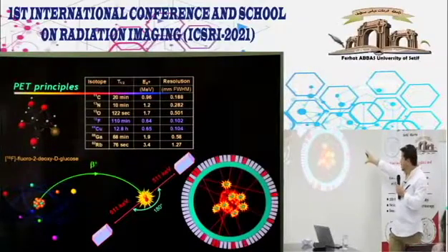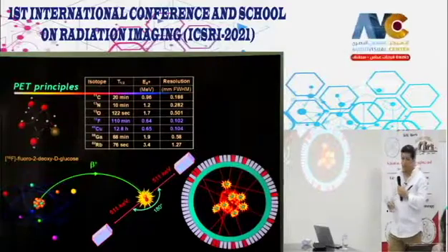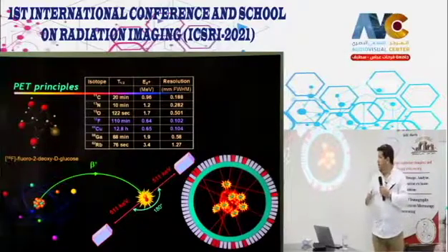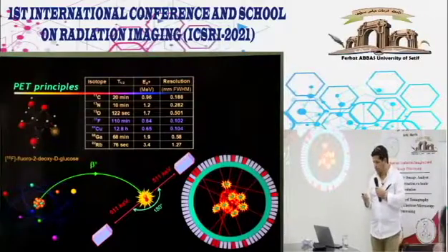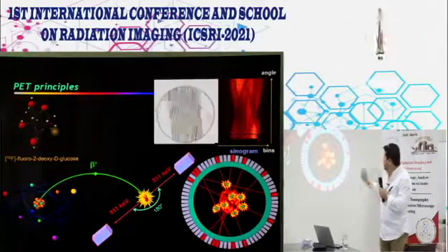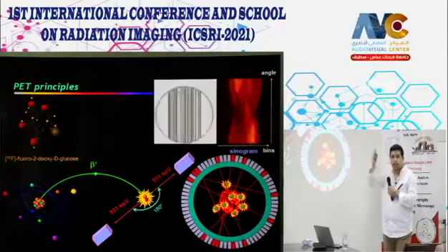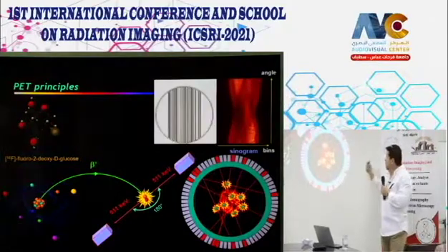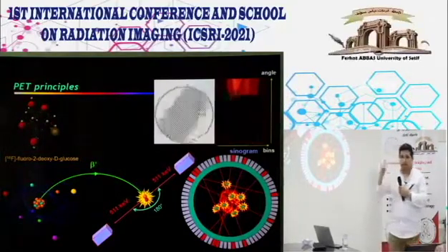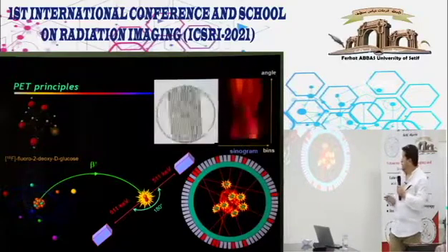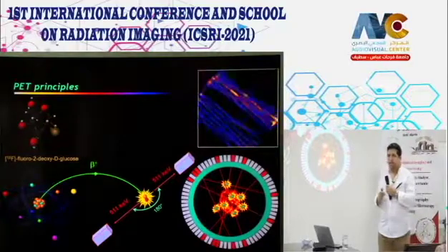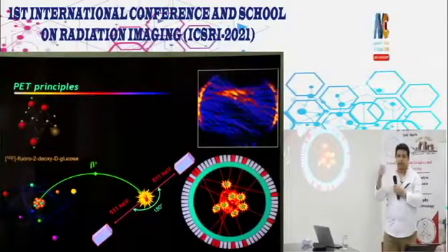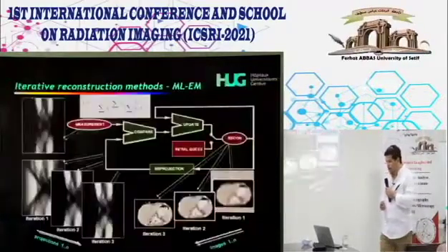And then we collect the data in coincidence mode, which means that we accept the events only if they fall within a specific coincidence window, which depends on the properties of the scintillation crystal. And then we record the data in exactly the same way, in sinograms. Each sinogram corresponds to what I explained before, and then we apply the same techniques to reconstruct the images from the measured projections, basically inverting the procedure as I described in detail.